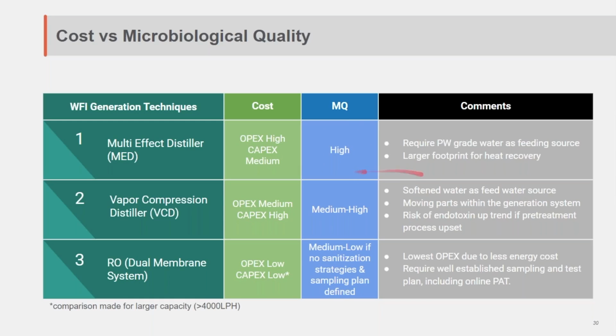However, the MED requires a purified water grade as a feeding source, as well as a larger footprint for heat recovery. When we move to the VC, or vapor compression distiller, you will have a medium OPEX, but relatively high CAPEX compared to MED or dual membrane systems. From the microbiological quality perspective, it's medium-high because we need to do certain maintenance on the compressor itself. If the system is being broken into in order to do the maintenance of the compressor, the moving parts or the system breaking will introduce airborne bacteria into it. And this is why normally a sanitization of the system is required post preventive maintenance.